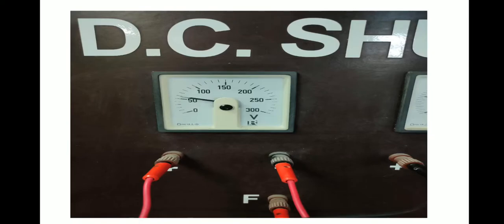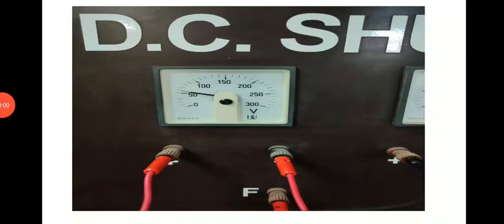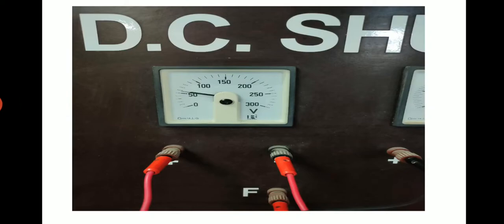Now before starting the machine I am providing a voltage of around 50 to 60 volts to the field winding of my DC machines. And this DC voltage will be delivered to the field winding only when the DPDT switch makes its contact with the terminals 2 2, that means the switch is in the run position.